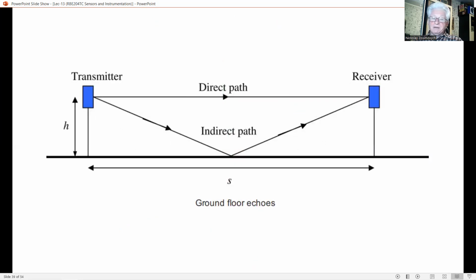In all these applications, special care should be taken with secondary echoes from the floor, walls, and other objects in the surrounding field. They may cause phase error and a shift in the envelope of the received signal, of which the consequences have already been discussed. This figure illustrates a situation where reflection via the ground floor may cause interference error.